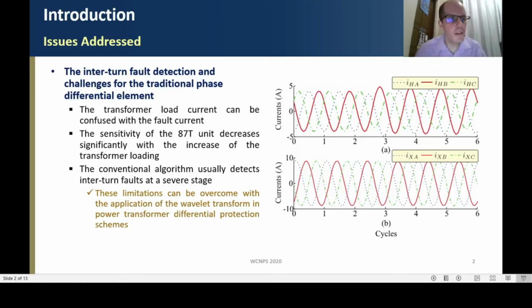The main issue addressed in this paper lies in the fact that interturn fault detection is still a challenge for traditional power transformer differential protection schemes, because the transformer load current in these faults in general can be confused with the fault current.